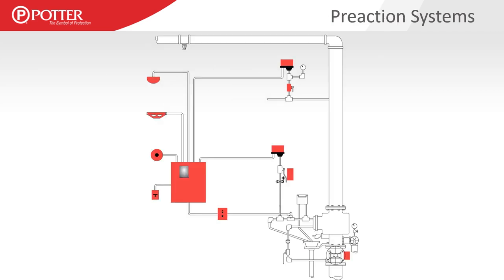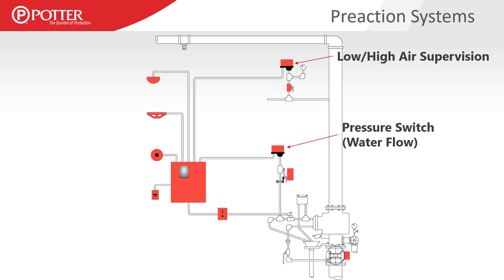Pre-action systems have their own special set of devices — we won't cover each of these today. A lot of these are typically fire alarm components, but for today's presentation we're going to continue to address the high and low air supervision, much like on the air side of the dry pipe valve, the pressure type flow switch — which is the same switch used on a dry pipe system and operates in much the same way.